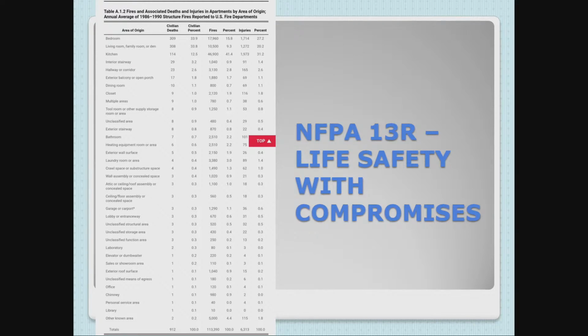You can't do it with a normal sprinkler system. You've got to put in a dry system or some other accommodation, or you've got to heat the attic. Well, heating the attic goes against the energy code, which is very forceful right now in our building code industry. So the codes basically said, you know what? We're going to design a system that from a life safety standpoint is like 98% effective. And that's what they did. And that's what we have to deal with.